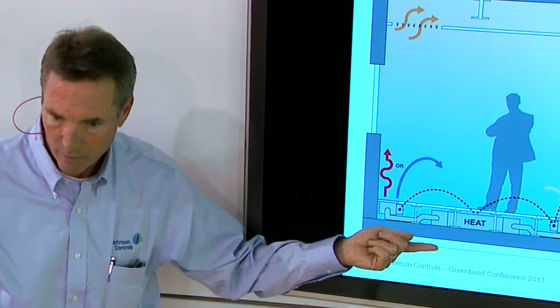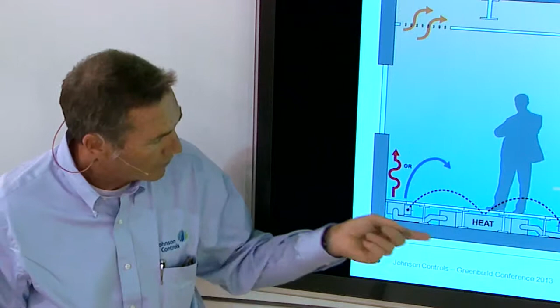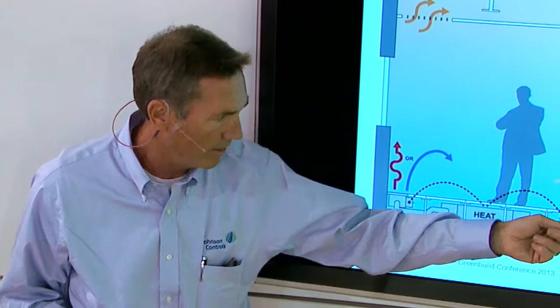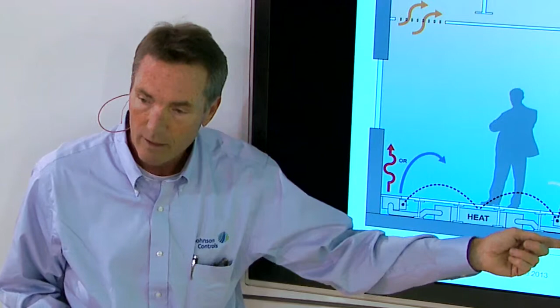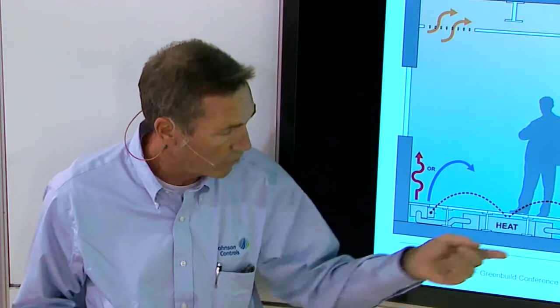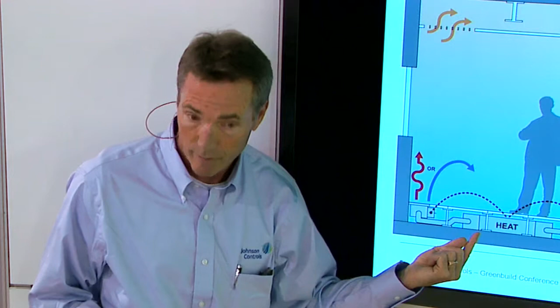The other learning here in terms of how do I maintain, how do I live with these buildings? With an underfloor system, it's quite different than an overhead ducted system. Overhead ducted systems, if you came in the morning as a contractor, how do I do early morning warm-ups? What you normally do is you'd put hot air into those ducts. Here, if we did that, if I took 90 degree or 100 degree air and put it under that floor, with all this mass in the subfloor, it would take a long time to heat it and then a long time to cool it back, so the building could start to yo-yo. So normally we want to just keep this consistent, rifle shoot in heat where you need it, like perimeters, like you see here. That's one of about a dozen which are highlighted in that guide.